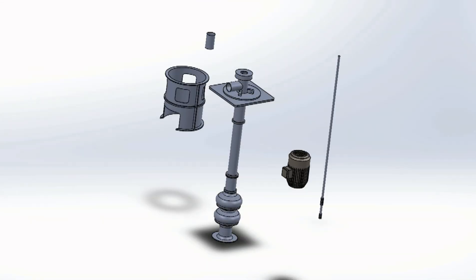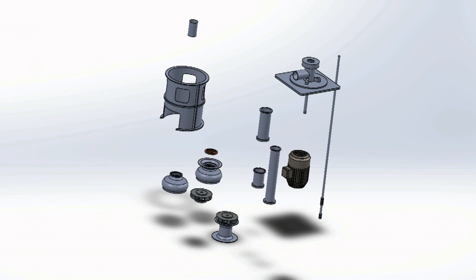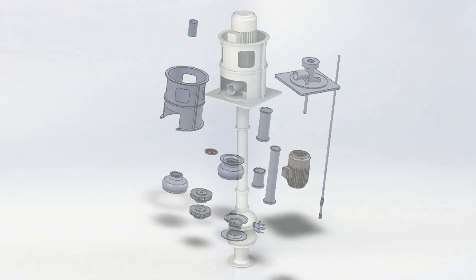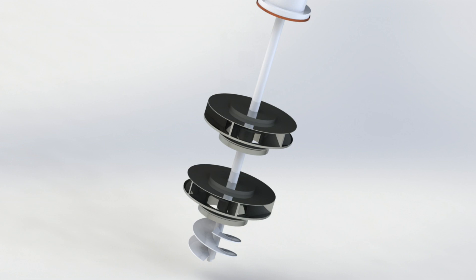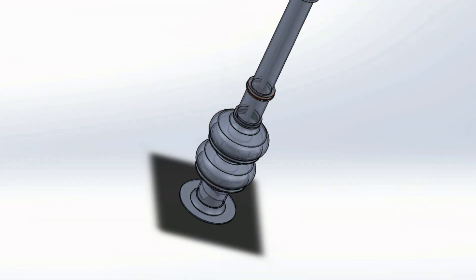The vertical impeller pumps located on the hot and cold salt tanks control the flow of the salt mixture to and from the tower receiver and heat exchanger. Two impellers spin at 1200 RPMs and generate a flow velocity of 5800 gallons per minute. The pump is engineered to accommodate thermal expansion due to high temperatures.